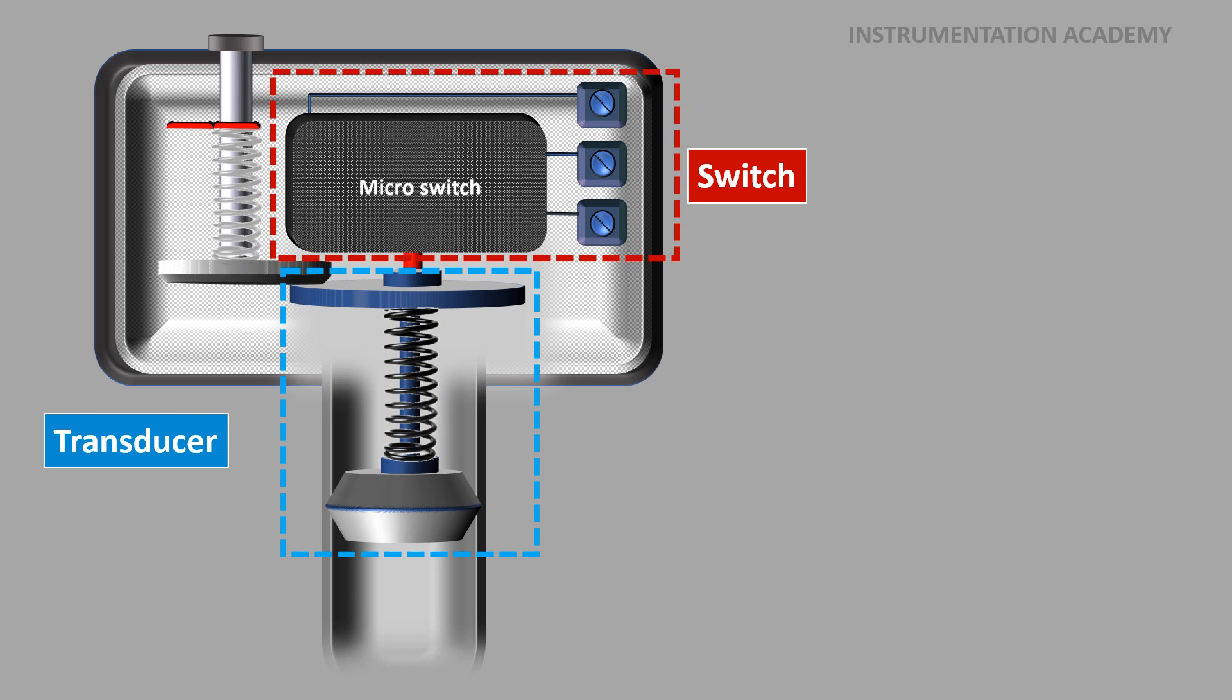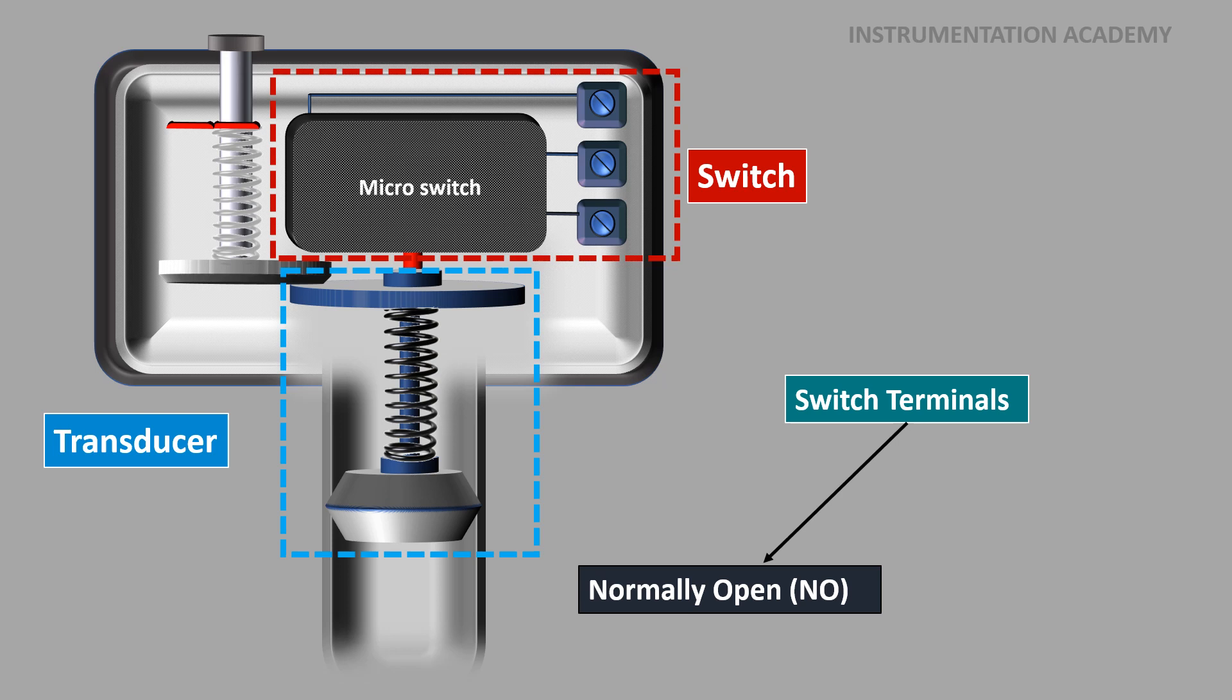Some switches have the switch terminals opened when no pressure is connected, which is called normally open switch (NO). When enough pressure is applied, the switch closes. On the other hand, some switches have the switch terminals closed when no pressure is connected, which is called normally closed switch (NC), and when enough pressure is applied the switch opens.